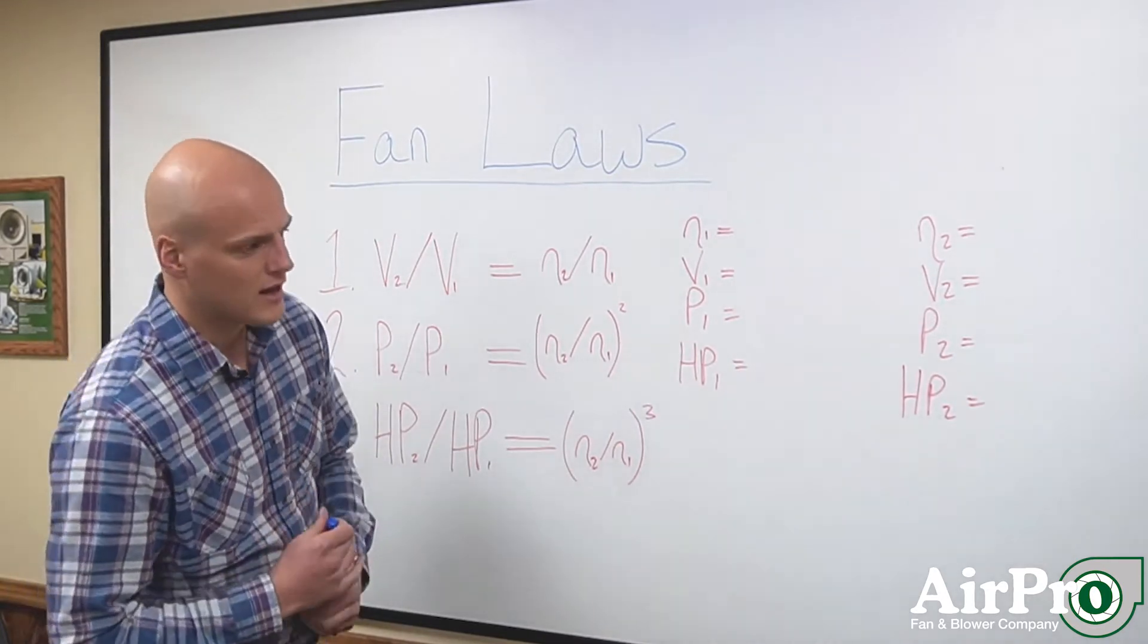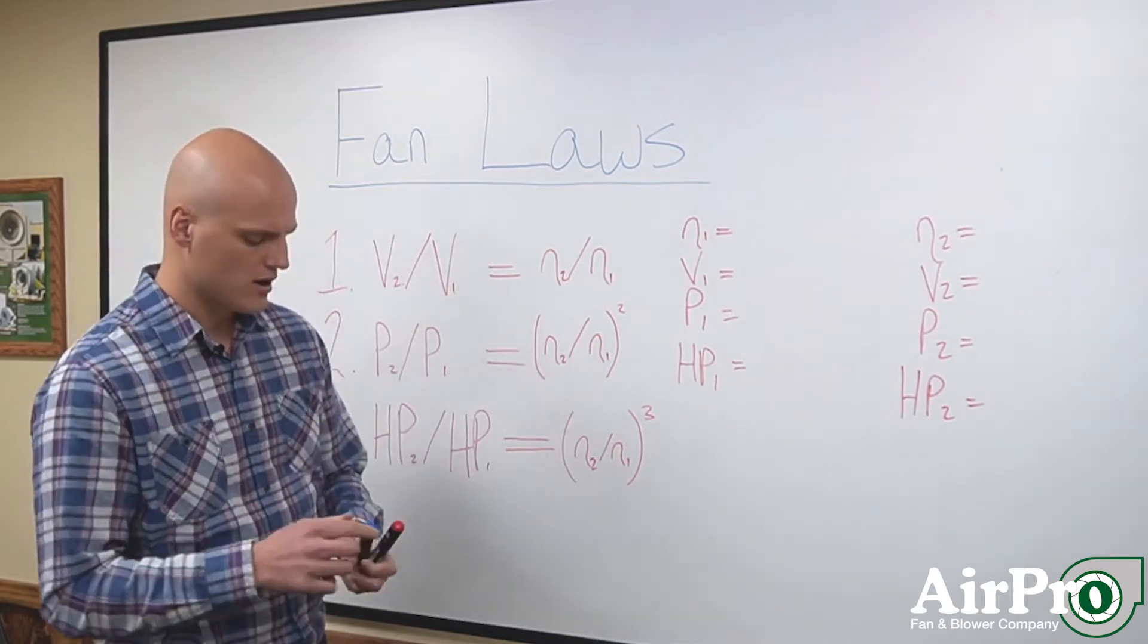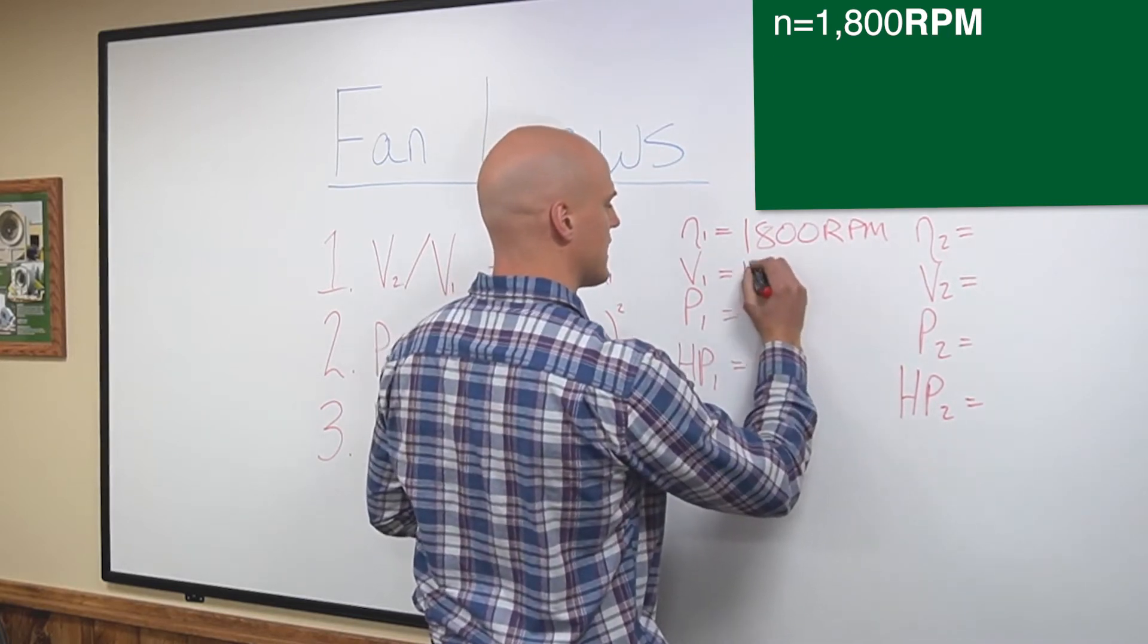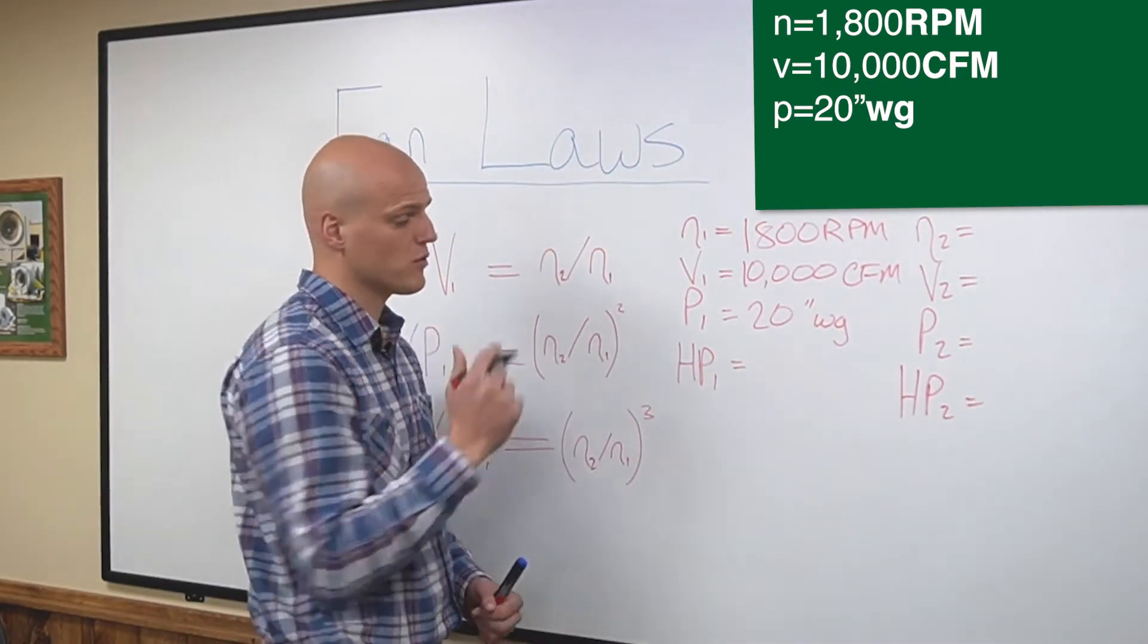Let's say you bought a fan and you knew that your operating point was going to be at 100 horsepower at 1,800 RPM. Your volume needed was 10,000 CFM, and your pressure needed was 20 inches of water. Your designed horsepower was 100 horsepower.